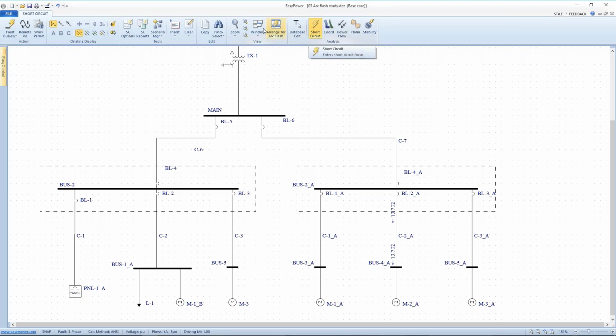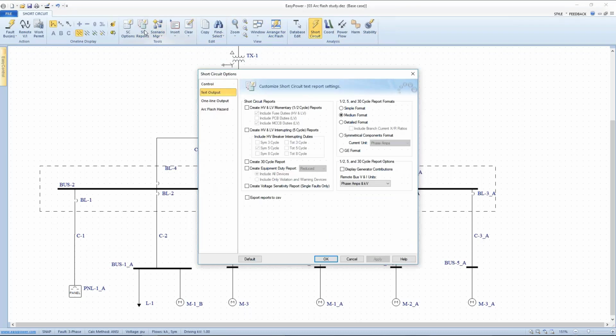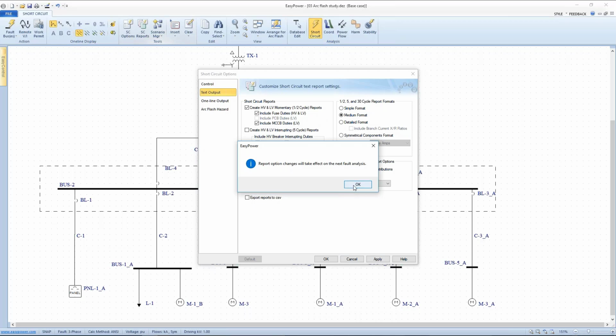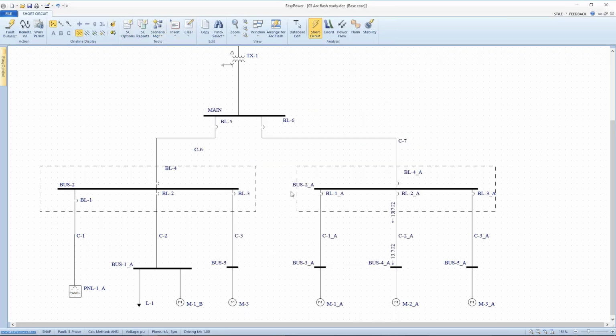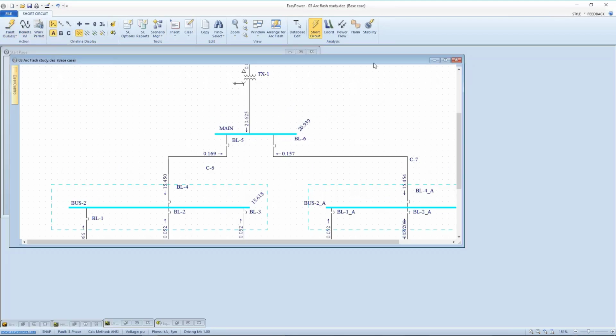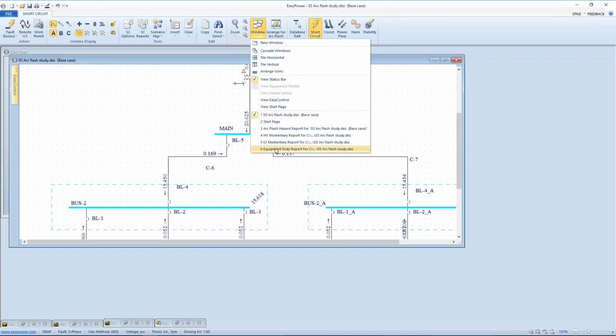I'm going to go to the short circuit focus, look at my short circuit reports, create a high voltage and low voltage half cycle report, create an equipment duty report, and let's go ahead and expand it and make everything medium format. And it says, okay, the next time you do a bus fault or a system fault, those reports will be generated. I'm going to create a fault all the buses. The window reduces because it's created all those reports and put them at the bottom of my screen. And we can look at those in turn.